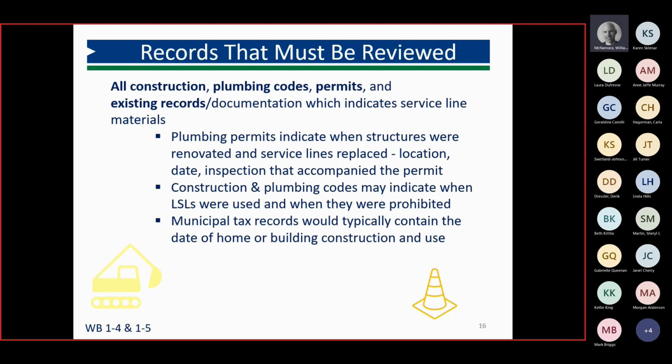Municipal tax records are going to be helpful because it will tell water systems when that home was built. So again, if it was built after the Pennsylvania lead ban went into effect, which was in January of 1991, then we know that that should not have a lead service line after that date.